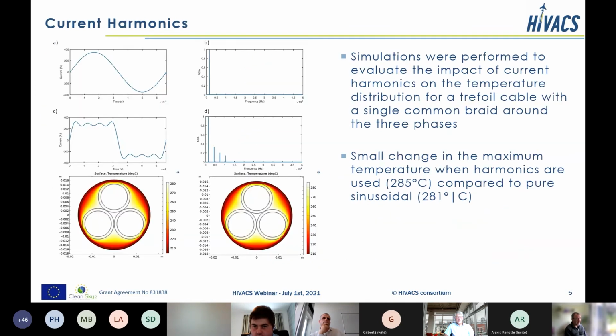So within the modelling, we had models that certainly worked, and I just want to pick out a few key results here that show you a couple of the things that we learned. First of all, harmonics can be significant, although they're not massively important. If you look at these two cases here, cases A and B. Case A is a pure sine wave. Case B is a much nastier high harmonic content waveform. And even with a fairly high level of harmonics, there was only a small change in the maximum temperature that we saw in these particular cables. So 285 compared with 281.